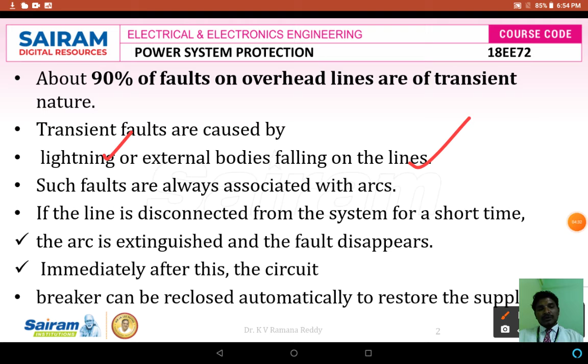Once either lightning strokes or external bodies fall on the lines, such faults are always associated with arcs. And if the line is disconnected from the system for a short time, the arc is extinguished and the fault disappears. Immediately after this, the circuit breaker can be reclosed automatically to restore the supply voltage, because once the fault is cleared, the circuit breaker has to close the switch, and again it is going to restore the supply voltage, increase stability, and provide continuity of electrical power supply. So definitely during the fault condition, the circuit breaker has to open the switch, and once the fault is cleared, the circuit breaker switch has to be closed.